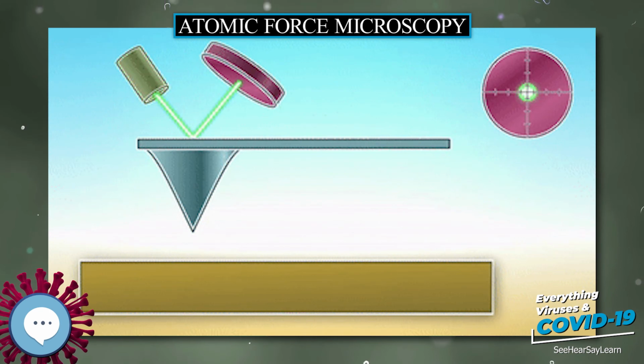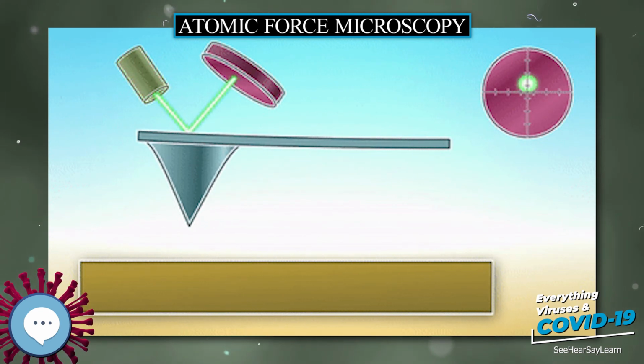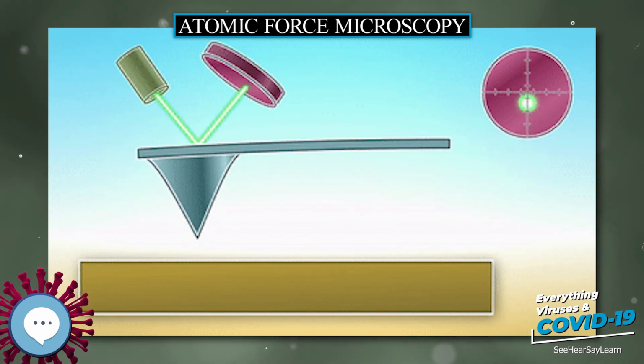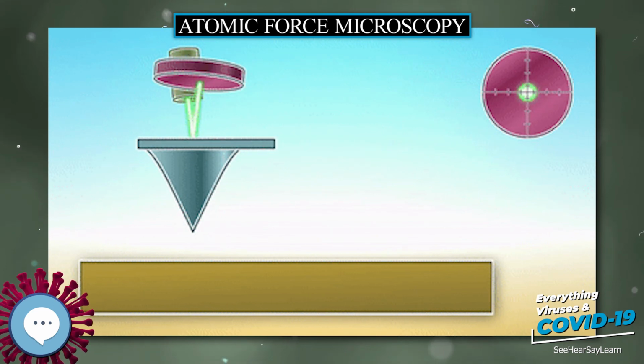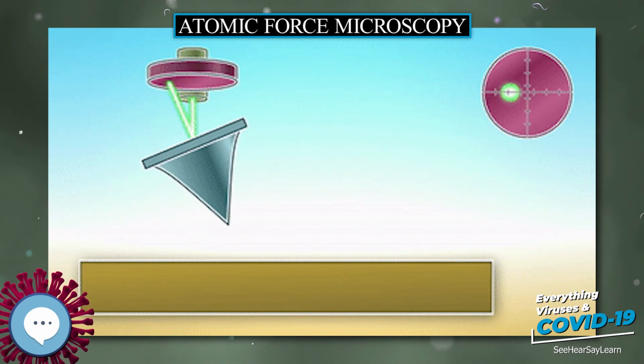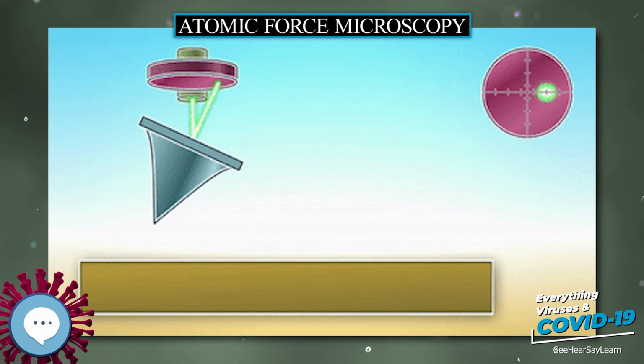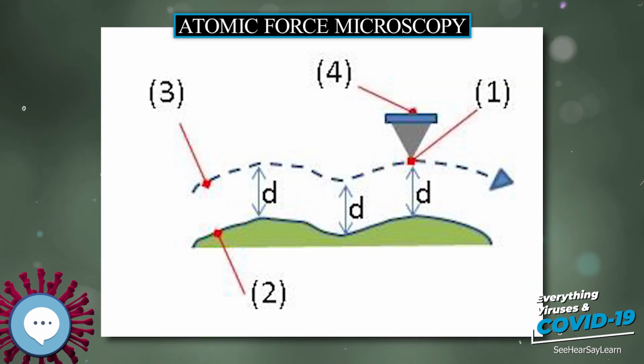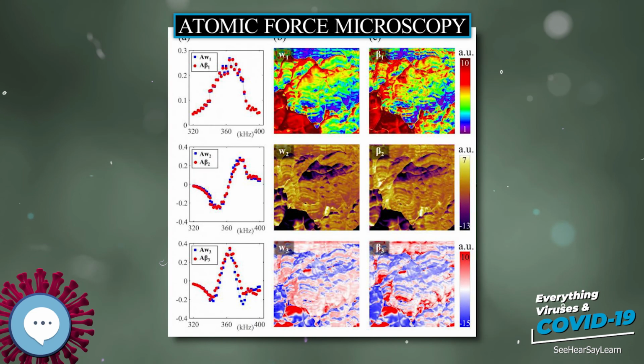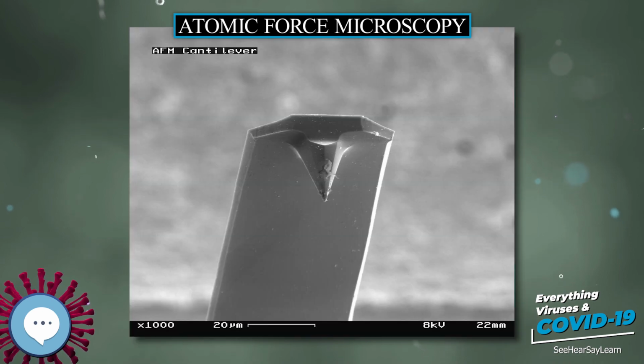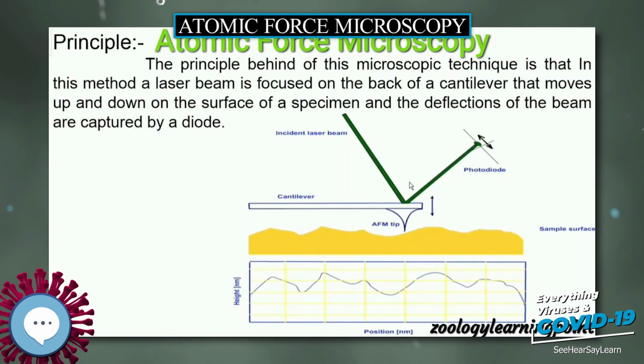It is however common practice to record the deflection even when scanning in constant force mode, with feedback. This reveals the small tracking error of the feedback, and can sometimes reveal features that the feedback was not able to adjust for. The AFM signals, such as sample height or cantilever deflection, are recorded on a computer during the XY scan. They are plotted in a pseudo-color image, in which each pixel represents an XY position on the sample, and the color represents the recorded signal.